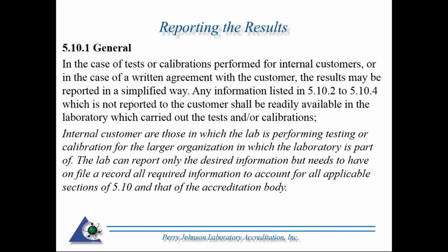So what this is stating here is that 17025 does allow for simplified reporting. That is, some of these elements could be removed from the calibration certificates. In the case, we'll talk about internal customers first. What are internal customers? Internal customers are those in which the lab is performing testing or calibration for the internal organization in which the laboratory is part of.